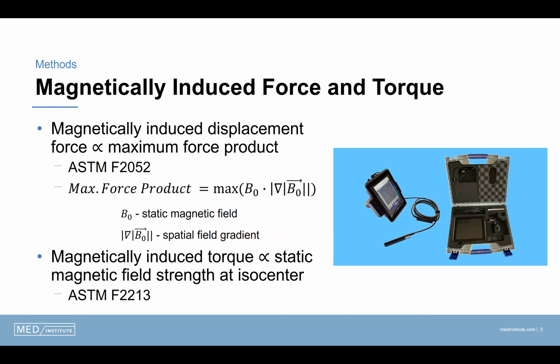The static magnetic field of each MRI system was mapped in 1 centimeter increments starting at isocenter out towards the control room using a Tesla meter. These measurements were then used to calculate the spatial field gradient. The force product at each measurement location was calculated as shown on the slide. The maximum force product for each MRI system was then used as the magnetically induced force metric, since this is where devices would be tested according to ASTM F2052, and because the force product is directly related to the magnitude of magnetically induced force of a given medical device.